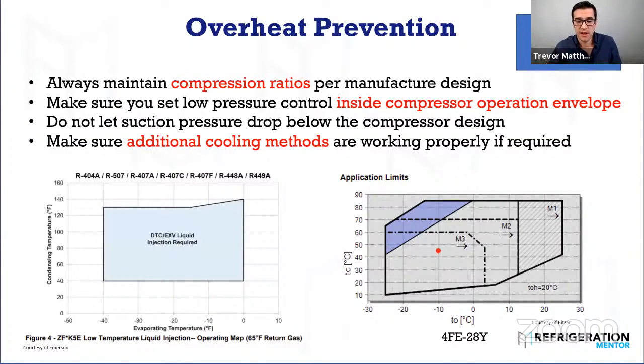So, other prevention: high superheat. If you have high superheat coming back, that could be causing your overheat. Maybe your TX valve is not opening. So grab the TX bulb, and you should see refrigerant start going through because you're heating up the TX bulb, which pushes on the pin to open up the valve. It's a whole other subject, but grab the TX bulb and you should start to flood that evaporator. If you don't, maybe there's something going on with the TX valve. You could have an undersized TX valve. You could have a plugged TX valve screen because you didn't properly purge. Lots of different things that you need to check. Solenoid malfunction, high superheat leads to high heat.